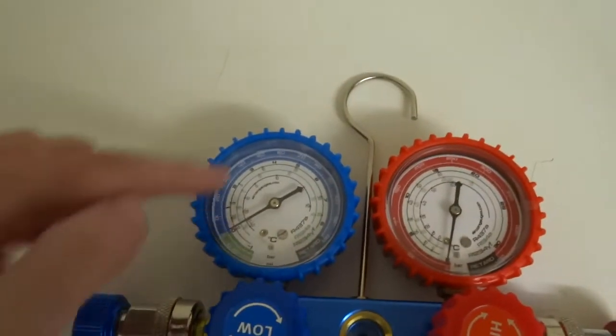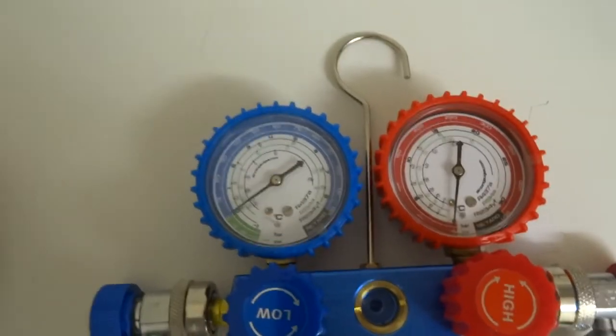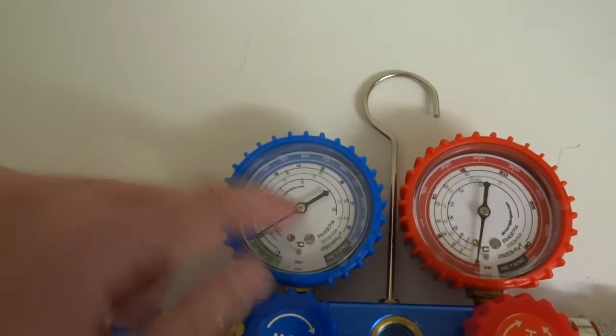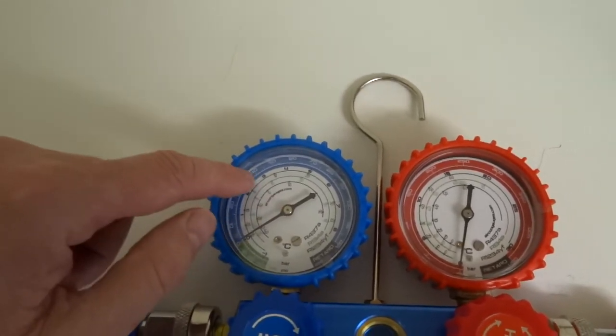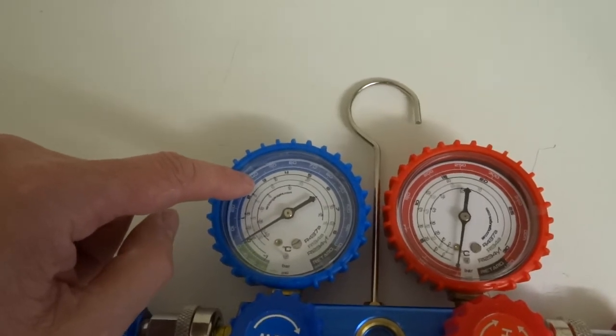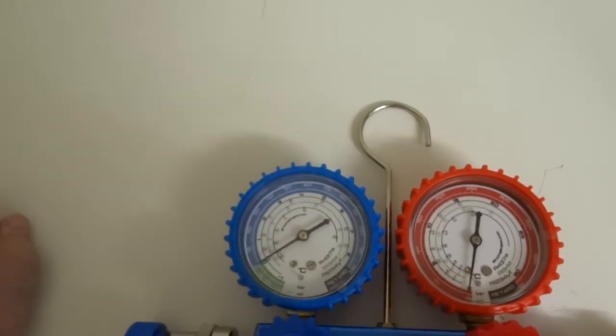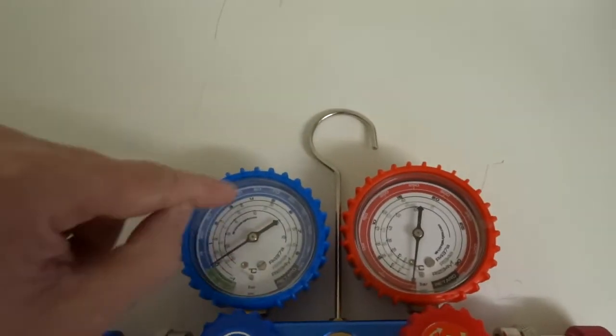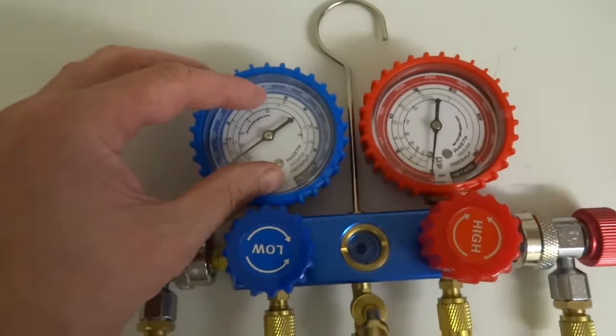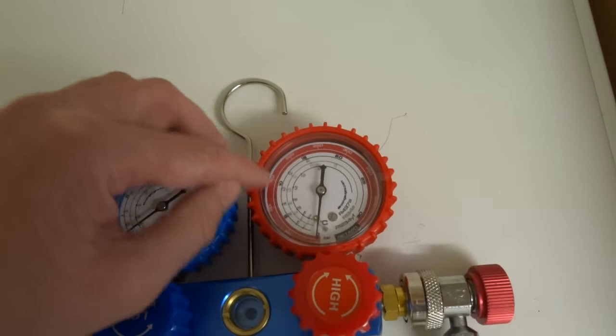Basically you can use that for more advanced fault finding. So say if you're at 35 psi on the low side, using 134A, that's about 4 degrees celsius. So you should check your evaporator and it should be about 4 degrees celsius.